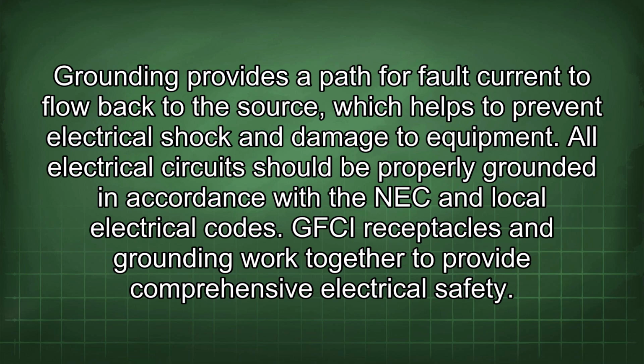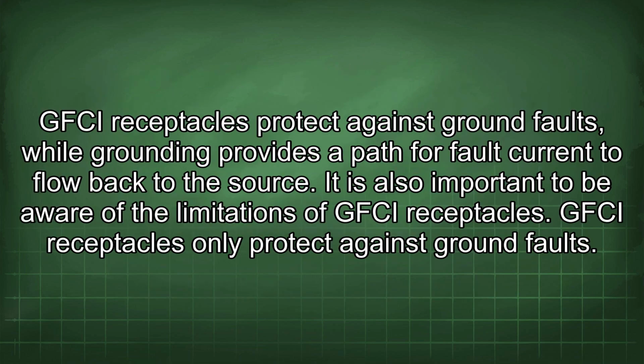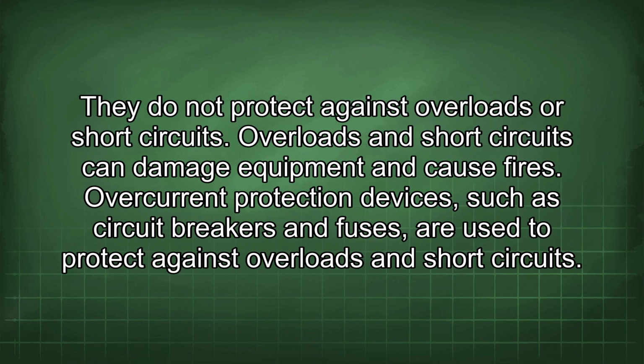GFCI receptacles and grounding work together to provide comprehensive electrical safety. GFCI receptacles protect against ground faults, while grounding provides a path for fault current to flow back to the source. It is also important to be aware of the limitations of GFCI receptacles. GFCI receptacles only protect against ground faults. They do not protect against overloads or short circuits.